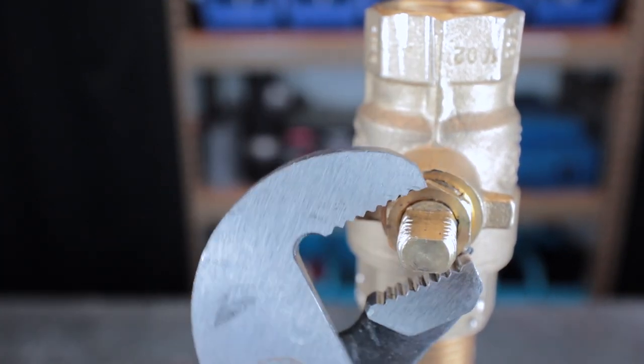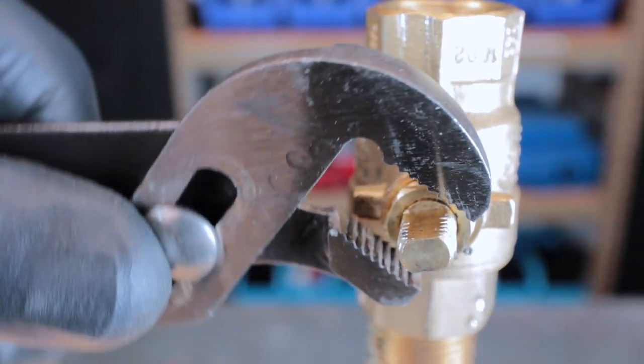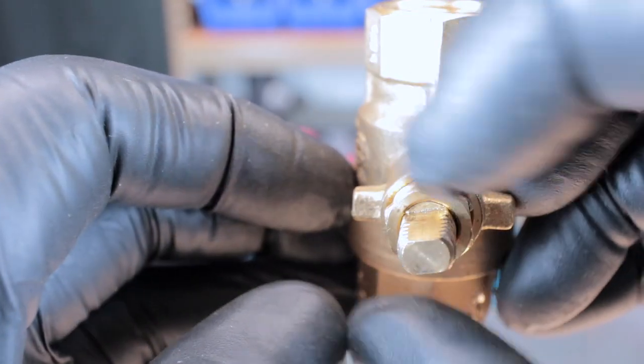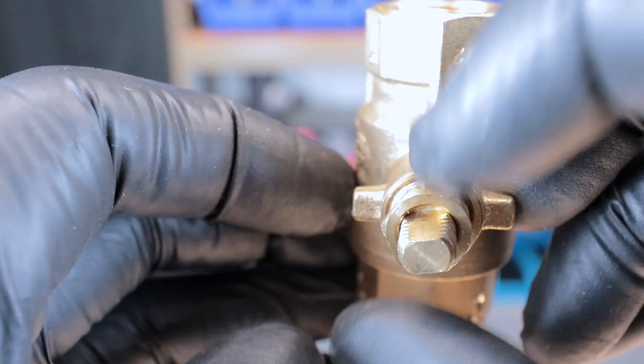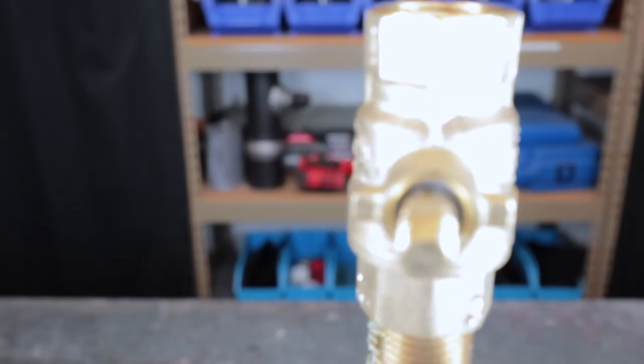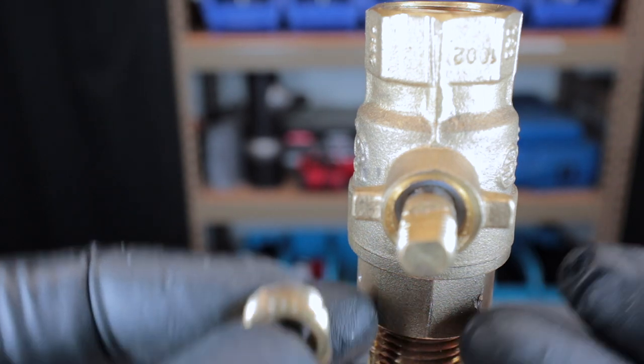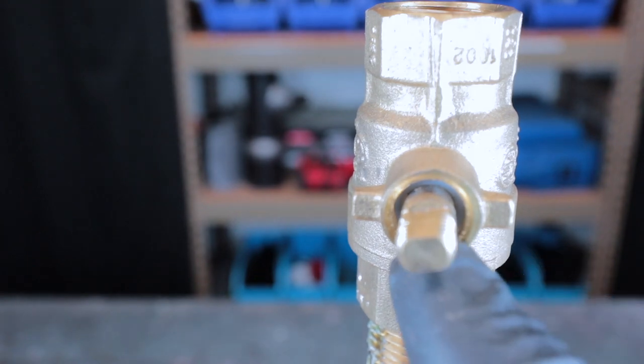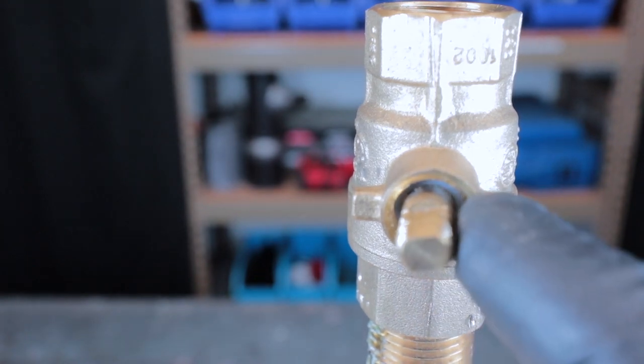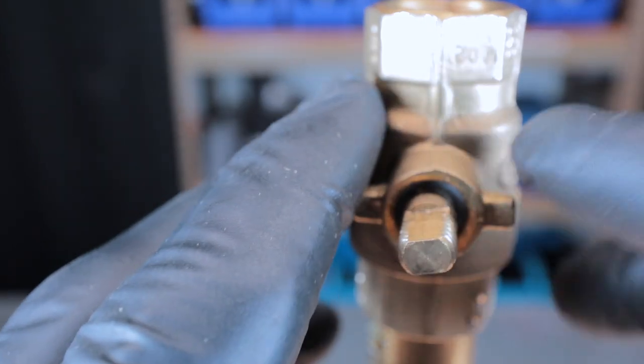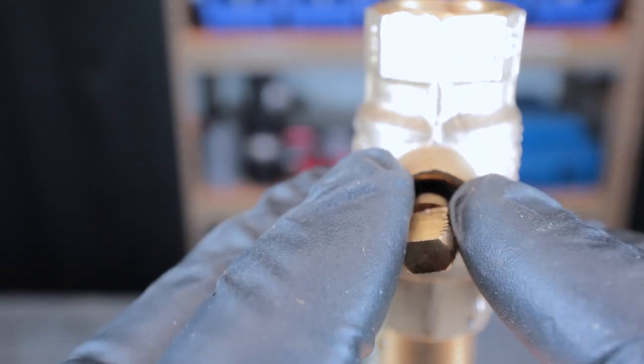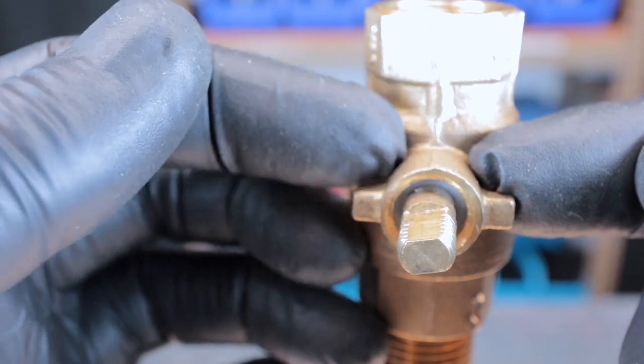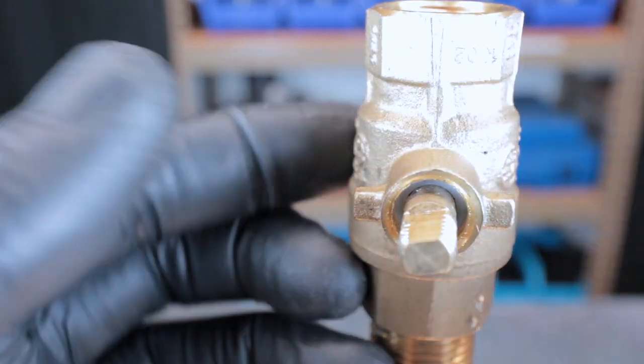It's simply a matter of coming in here with either an open end wrench or in this case I got my little mini channel locks and I'm going to back off this packing gland. Bear in mind this valve is in the off position. As I loosen this, depending upon the condition of the packing that's in there, it may start to drip or dribble a little bit. It's not a big deal, but if you're uncomfortable with that then shut the water down. In here there is a nylon washer set all the way in there. That's to keep the packing from actually entering the valve body.